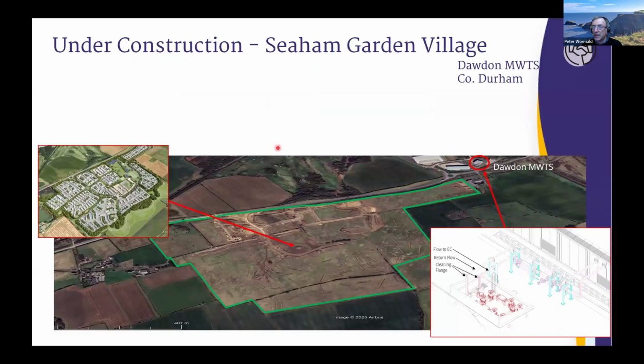Turning to Seaham Garden Village, which is a large waste mine water heat project under construction. We're really pleased that's powering ahead. And that draws on the field trials that we talked about at the Dawdon Mine Water Treatment Scheme, and is now building a large heat network, something over 1 kilometre in length, to the final development when completed. And we anticipate that will be by autumn this year. At the bottom, you can see the pipework connections to the energy centre, the flow and return flow lines which connect to the mine water treatment scheme.